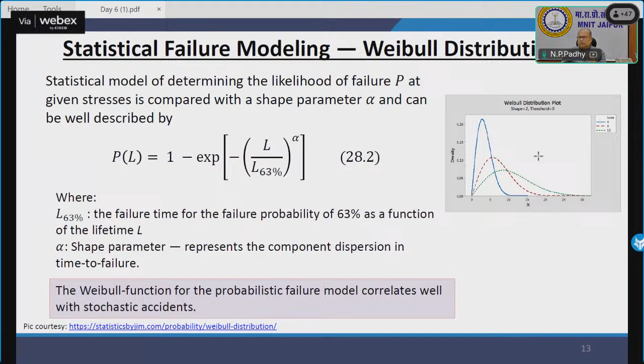We need to do research and try to understand which function fits. Once you get equation 28.3, it models failure probability as a function of combined electrical, mechanical, and thermal stress. Temperature has the most significant impact, increasing failure probability exponentially - it's one of the very important challenges. Electrical and mechanical stresses also contribute negatively, and at high temperature, insulation becomes so degraded that electrical stress directly causes failure rather than gradual aging.